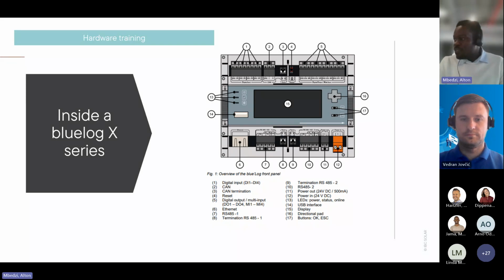Each RS-485 interface, especially, I want to touch on this because it's very important: each RS-485 interface supports only one single protocol, for example Modbus. So you can have different manufacturers on one RS-485, however it's not something we'd recommend because it reduces the performance and quality of monitoring and power control functions.